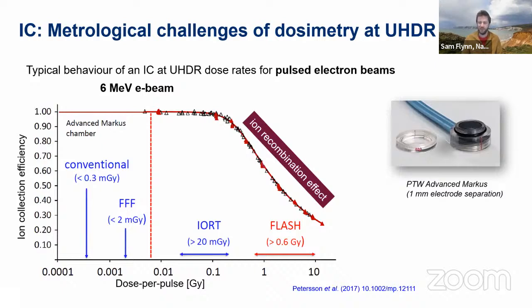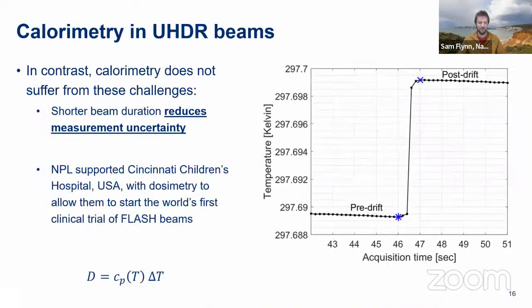So make sure you get it right. Don't overdose and underdose a patient. Be really certain of your dosimetry. There are obviously some instruments that aren't dose rate dependent, that don't have this ion collection efficiency like ion chambers do. I've spoken about them earlier. It's my favorite: calorimeters. Because we're just putting radiation into a medium and causing a temperature change, more radiation faster isn't causing any issues. If anything, it makes the calorimeters perform better.